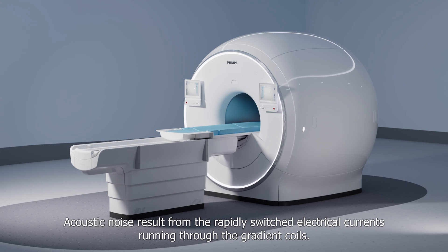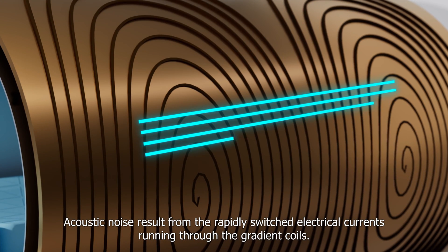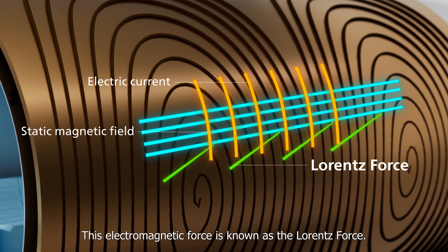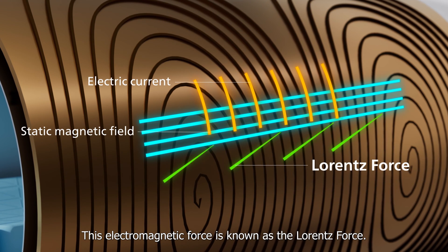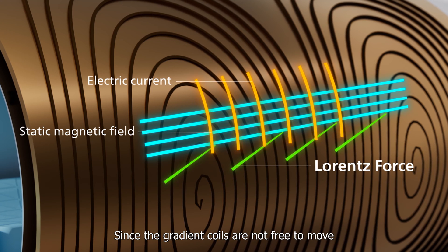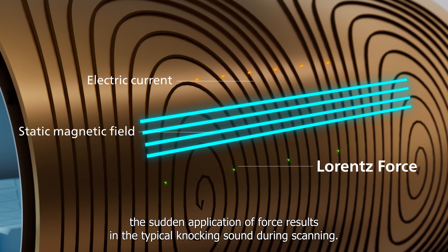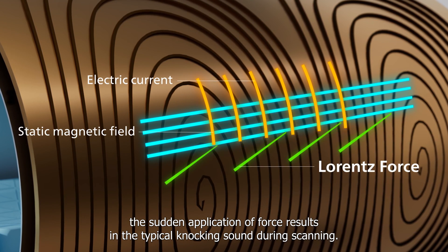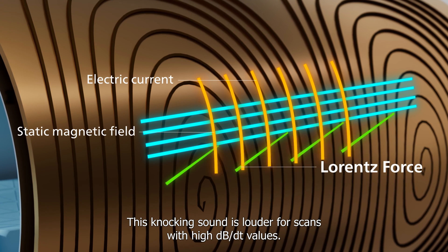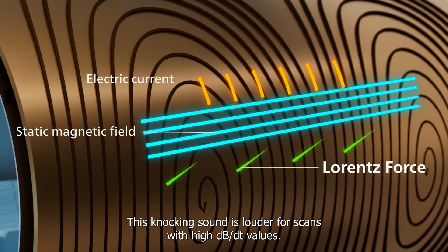Acoustic noise results from the rapidly switched electrical currents running through the gradient coils. This electromagnetic force is known as the Lorentz force. Since the gradient coils are not free to move, the sudden application of force results in the typical knocking sound during scanning. This knocking sound is louder for scans with high dB/dt values.